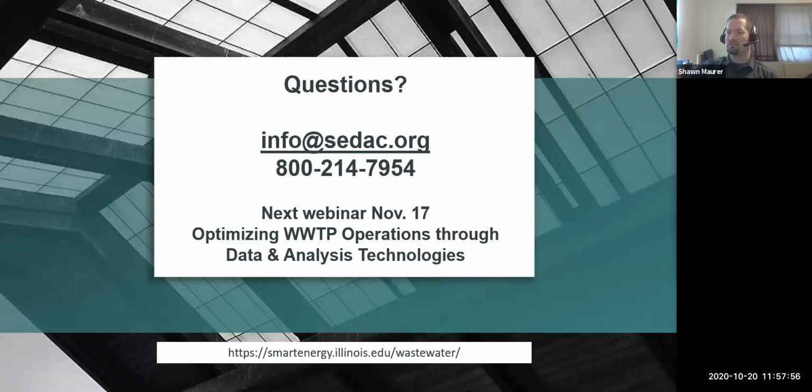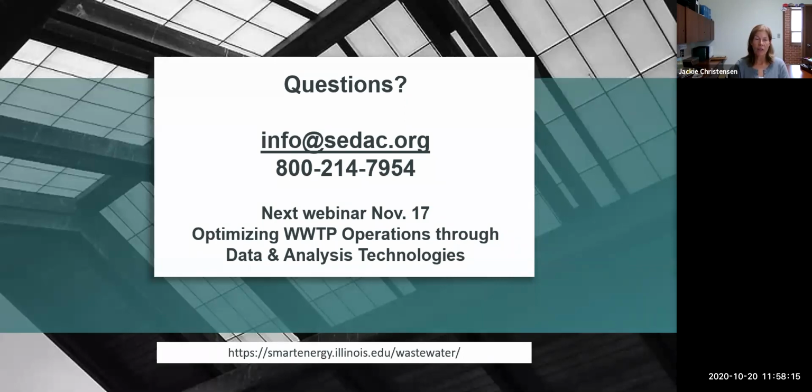We have a question for Jackie. Do the tertiary filters also assist with phosphorus removal? And if so, is it a significant reduction? We've had some issues when we take the nitrification tower offline and dry it out, you put it back online, it's going to slough off a lot of that organic material. And we'll see loading on the filters.